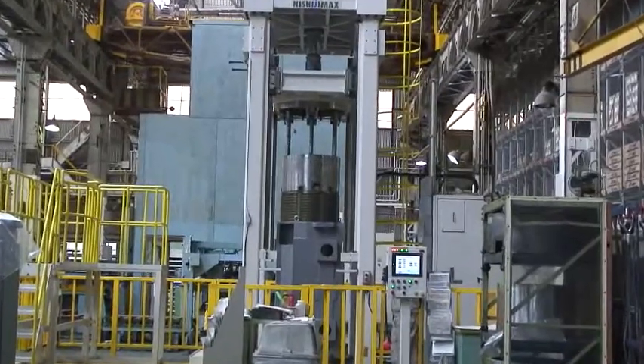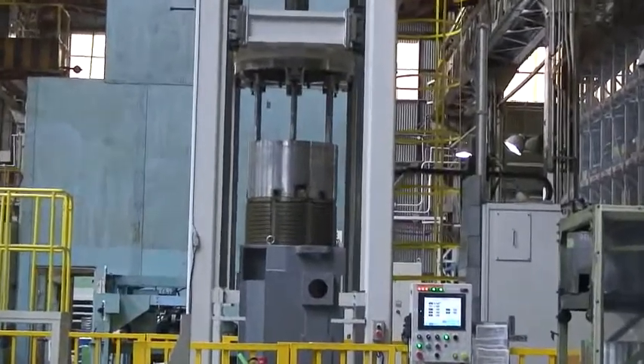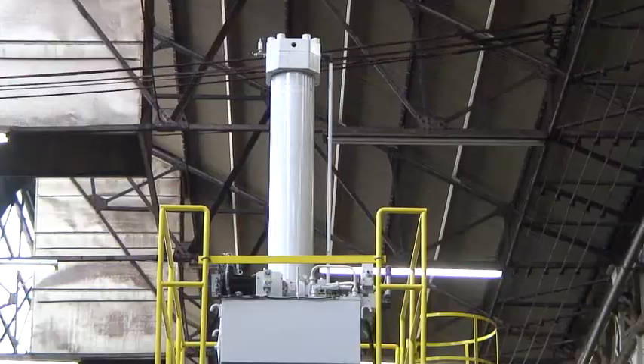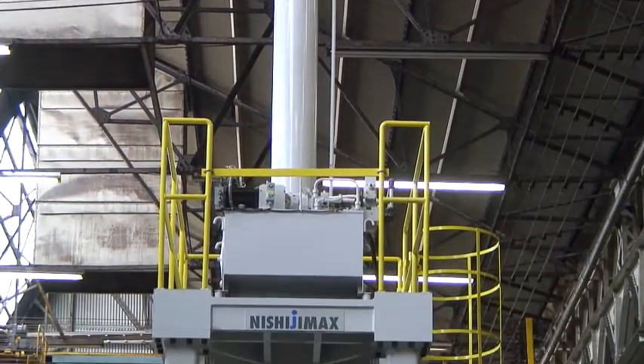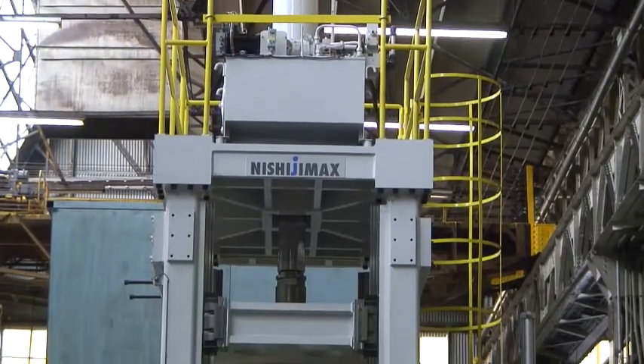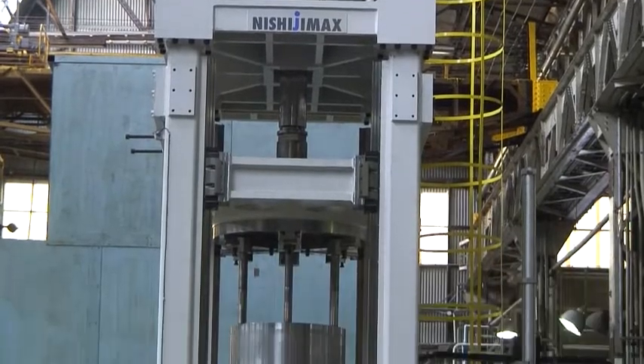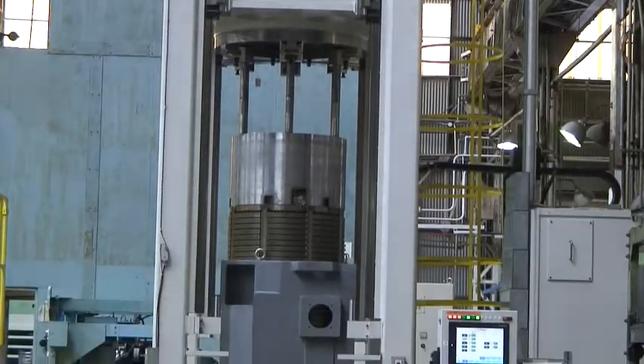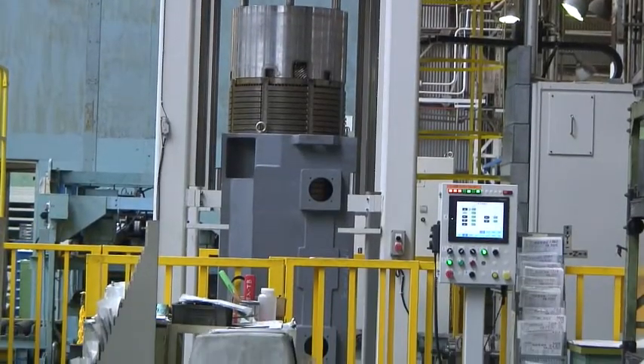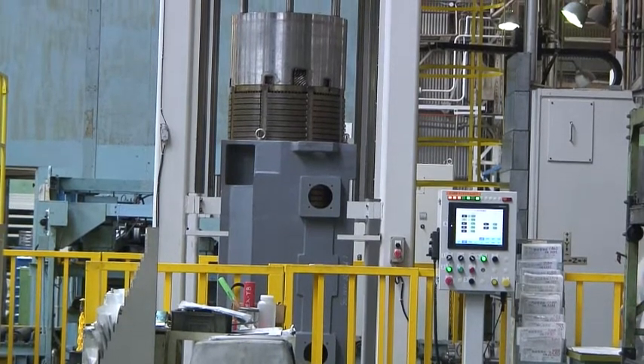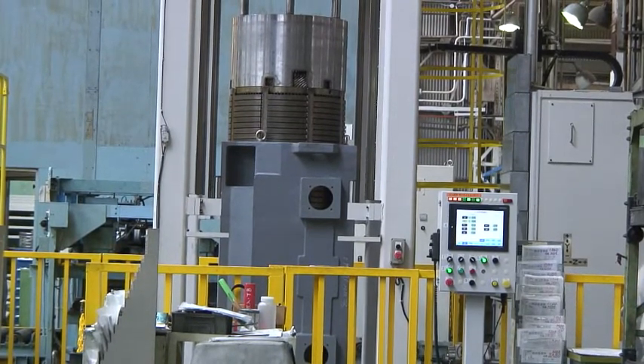This automatic machine in the Nagasaki plant inserts stator cores into the shrink fit frame and compresses them with a hydraulic ram. The insertion accuracy is to within 1 millimeter, and the system has feedback control of the frame length. No operator is required during the whole insertion process until at the end, when the lock pinhole is machined.